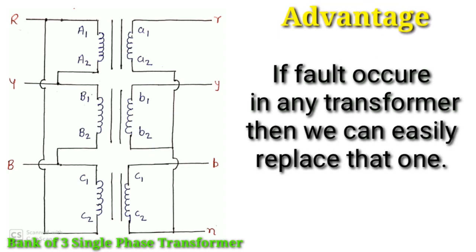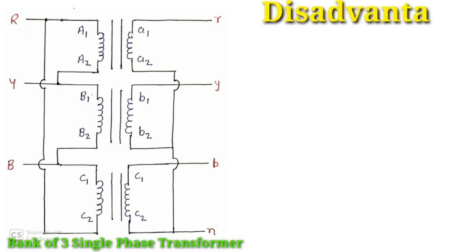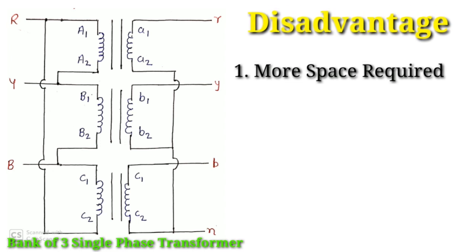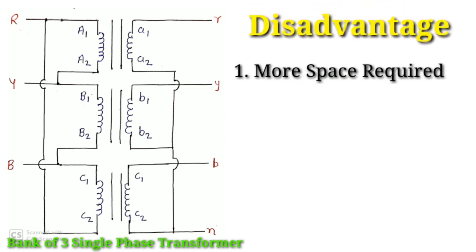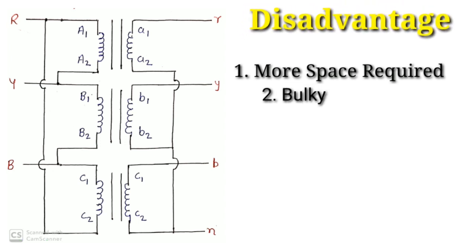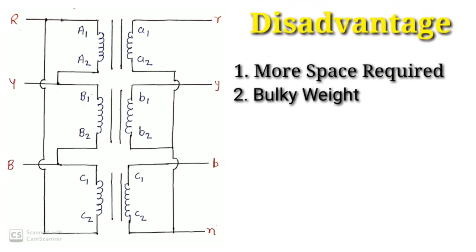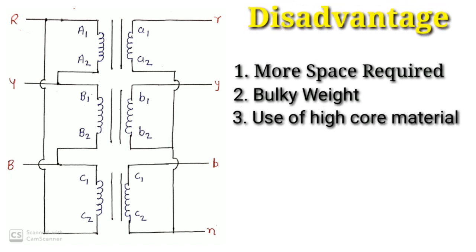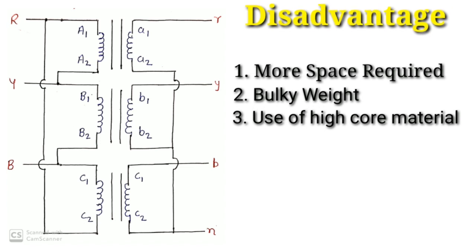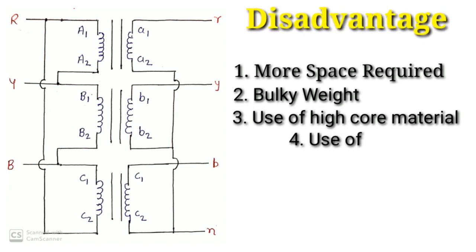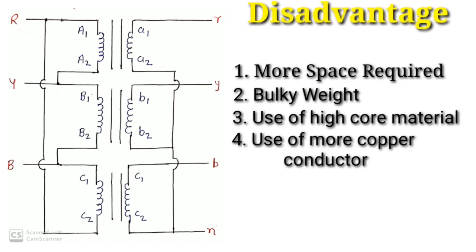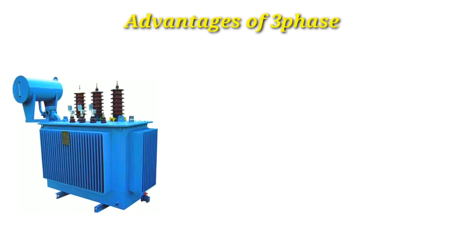These are the advantages of the bank of three single-phase transformers. Now some disadvantages: first, more space is required for this bank. Second, the overall weight of the bank is more. Third, since there are three transformers, three cores are needed, and more copper conductor is also required for all three cores.